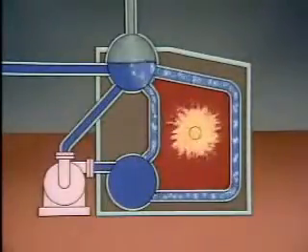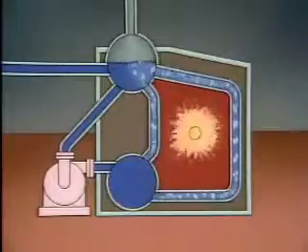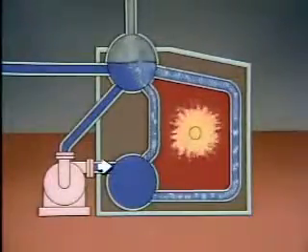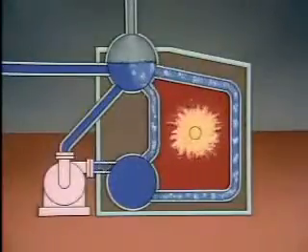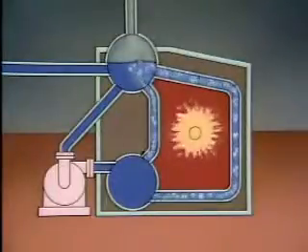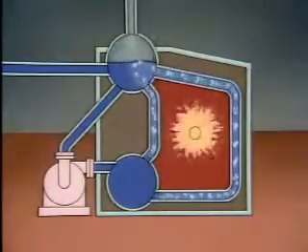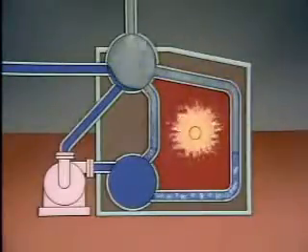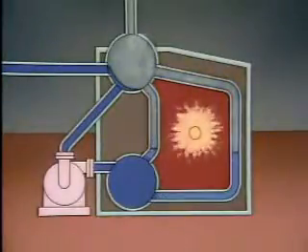As the water in the risers is heated, a steam-water mixture is produced. Water from the pump forces the steam-water mixture into the steam drum. If the pump stops, the water will no longer circulate properly and the boiler could boil dry and become damaged. To ensure proper water flow, most controlled circulation boilers use two or more pumps so that even if one pump stops, the other provides enough circulation to prevent damage to the tubes.